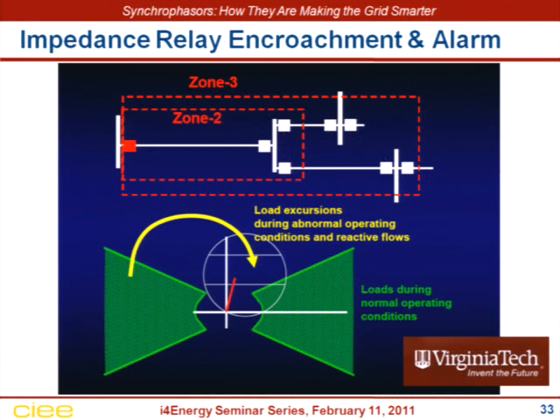This is the relay, impedance relay zone encroachment. If you can see this, the zones on a relay, each relay has a primary zone and a backup zone. The primary zone, what that says is, if the fault is closest to this relay, it should trip first, instantly, fast. If it doesn't, if it fails somehow, then relays that are farther away, after a little bit more time, will then trip and clear that fault. So it's backup protection.